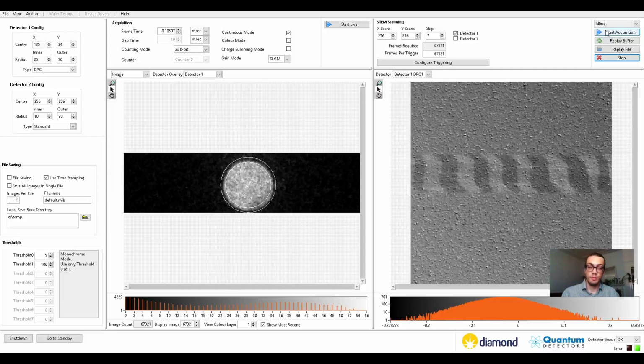As my final note, I would like to mention that we are continuously improving abilities of our software and the improvements are available to our customers. In the newest version of our software, we introduced a search mode with which a continuous scan can be performed and beam alignment is easy to do even with a 4D STEM acquisition. This becomes practical due to the speed improvements available through the region of interest mode.